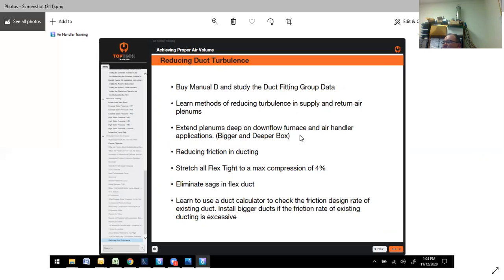Extend plenums deep on downflow furnace and air handler applications. That goes as well for an upflow. You don't want a 6-inch plenum before you take a hard takeoff. Reduce friction in ducting. This is a good one. Stretch all flex duct to max compression of 4%. You don't want a bunch of sagging spaghetti flex duct. And also you have to learn to size the flex duct according to what you're truly wanting to achieve.